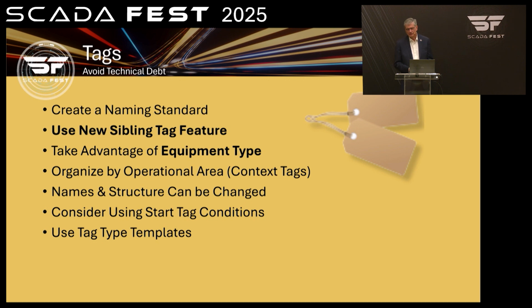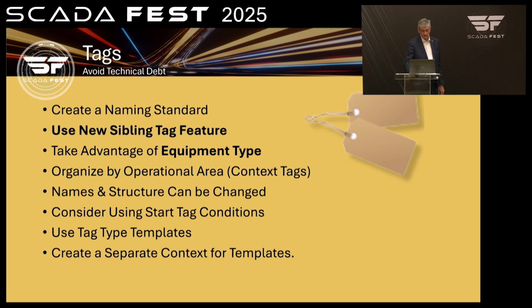We set up templates using what I'd call design by example. The idea is you create one tag tree, one context with all the tags underneath it that actually works, and then you hit an option to create a tag type from that. So you have this one tag tree, and once it all works, that becomes your template. Everything else after that is essentially an instance of that template, so if you change the template in the future, everything else just follows.